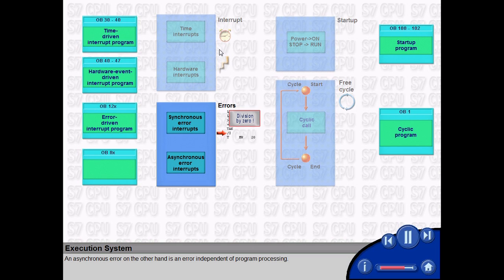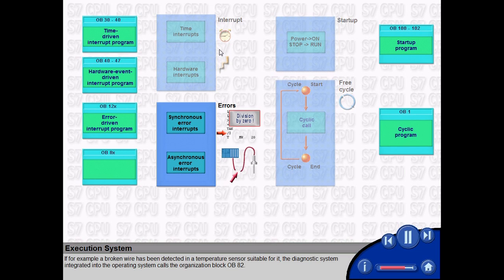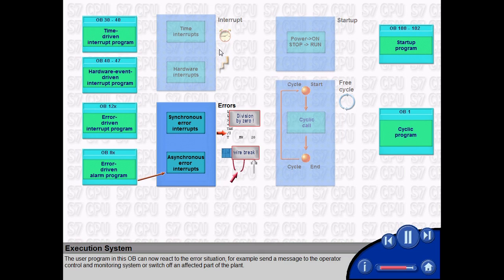An asynchronous error, on the other hand, is an error independent of program processing. If, for example, a broken wire has been detected in a temperature sensor suitable for it, the diagnostic system integrated into the operating system calls the organization block OB82. The user program in this OB can now react to the error situation.